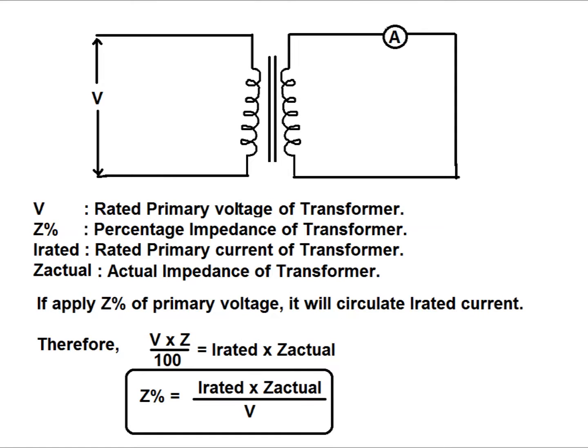If V is the rated voltage of the power transformer, Z percent is the percentage impedance, I rated is the rated primary current, and Z actual is the actual impedance of the transformer — then applying Z percent of the primary voltage will circulate I rated current in the secondary side. Therefore, V × Z / 100 = I rated × Z actual. Therefore, Z percent = (I rated × Z actual) / V. That is, it is the ratio of the rated voltage drop at rated current to the rated voltage.